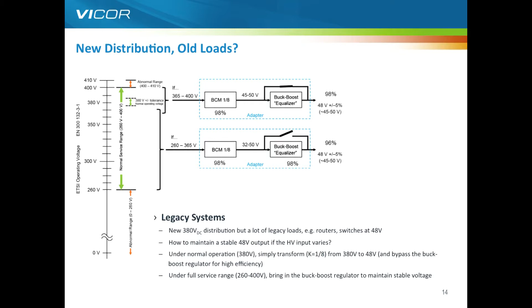While we're looking at the data center area, we also need to think about people moving away from traditional 12 volt distribution on the motherboard to something higher. Putting 380 volts onto a motherboard is possible, but getting that close to the processor starts to worry people. However, we do have an established 48 volt direct-to-processor combination, originally pioneered in telecom and now adopted in the server market, converting power from 48 volts very efficiently down to 1, 1.8 or 0.9 volts. Here's a quick snapshot of some Intel-based reference designs where Vicor units provide very efficient, very low-cost power from that 48 volt rail down to 1.x volts. We'll go into more detail on that in the market-specific webinar.